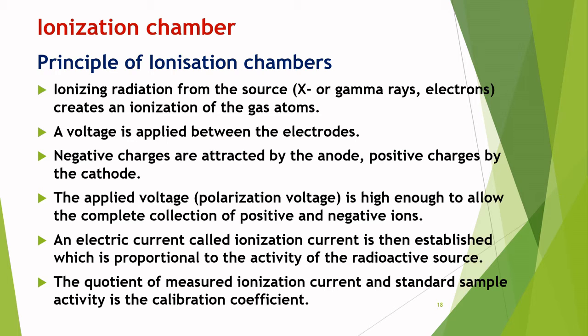Ionization chamber. Principle of ionization chamber. Ionizing radiation from a source such as gamma or X-rays, or electrons, creates ionization of the gaseous atoms. A voltage is applied between the electrodes. Negative charges are attracted by the anode, whereas positive charges are attracted by the cathode. The applied voltage, or polarization voltage, is high enough to allow the complete collection of positive and negative ions. An electrical current called the ionization current is then established, which is proportional to the activity of the radioactive source. The quotient of a measured ionization current and the standard sample activity is known as the calibration coefficient.